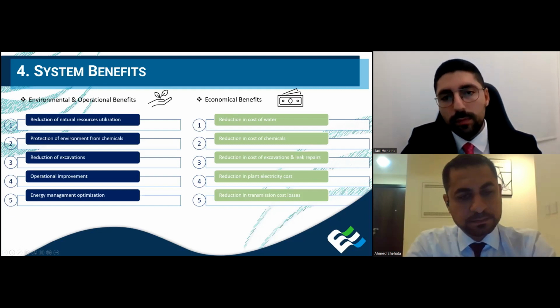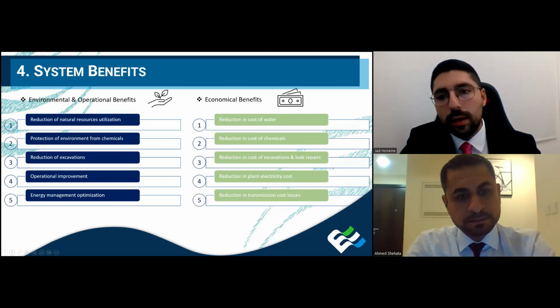Similarly, from an operational improvement perspective, reducing chilled water leakages improves transmission losses across the full network and improves energy management. All of these points translate into economical benefits, including reduction in the cost of lost water, reduction in the cost of chemicals lost through leakages, reduction in excavation and leak repair costs, and improvements in transmission losses and plant electricity costs from an operational perspective.